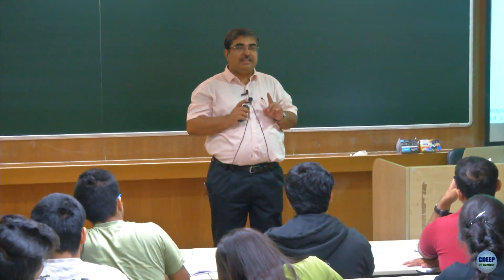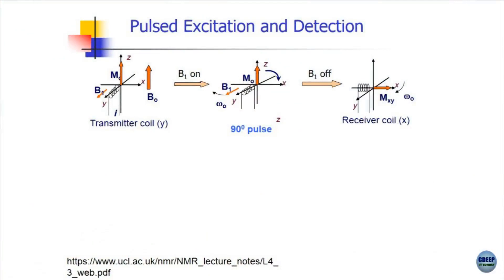You apply the 90 degree pulse, then you see a big signal in the detector. The 90 degree pulse means the radio frequency is turned on, the bulk magnetization vector rotates, and then it is switched off. At the moment the RF gets switched off, you get this big signal in the detector. After that there is no radio frequency — what you have in the system is the bulk magnetization vector now along X (where the detector is) and you still have B0.